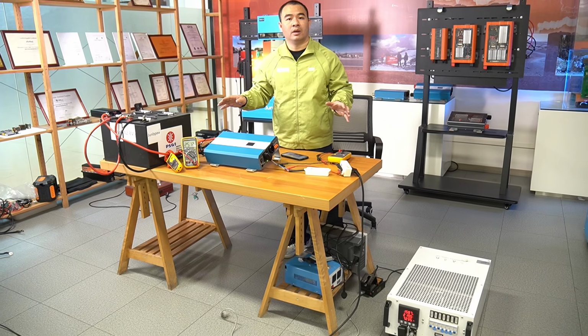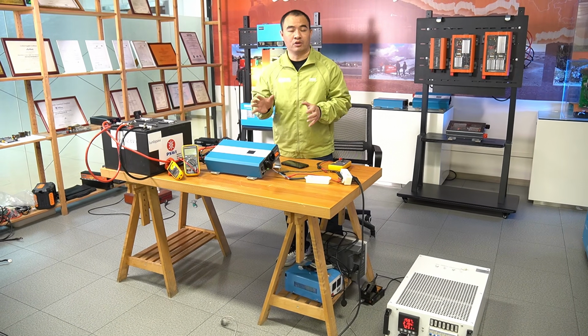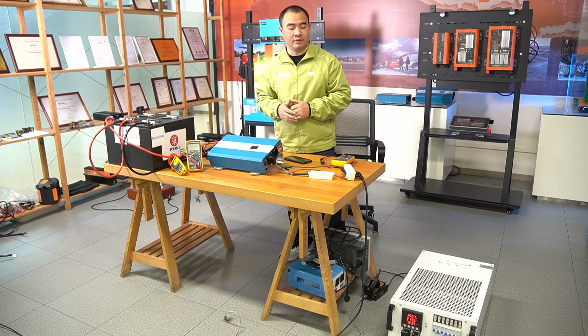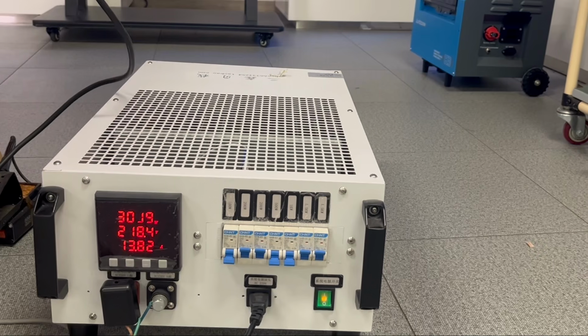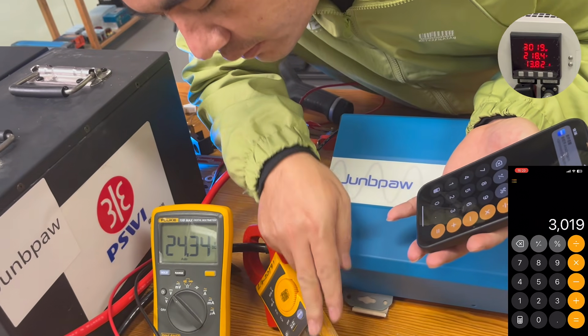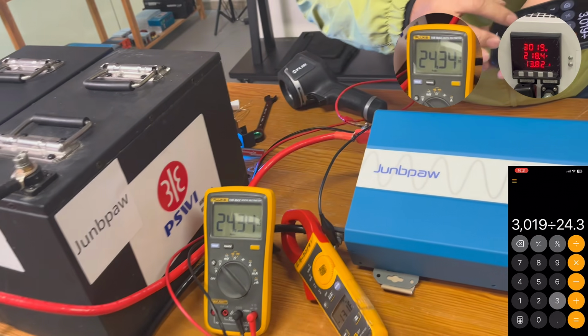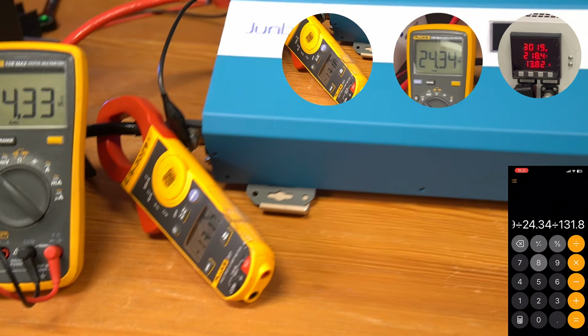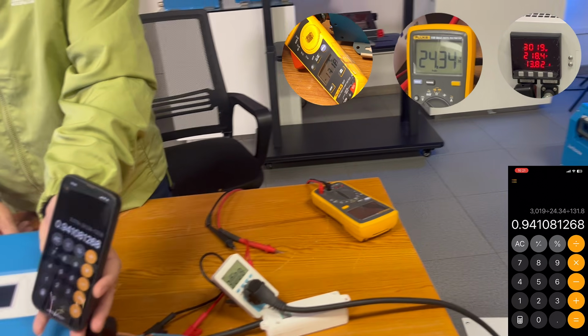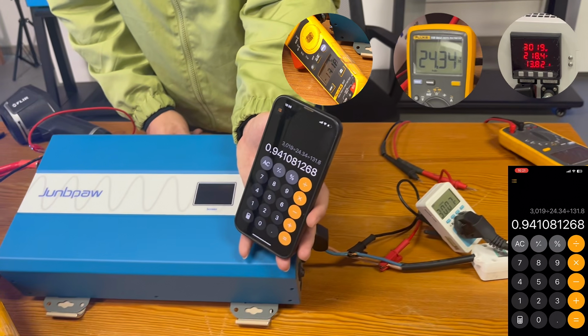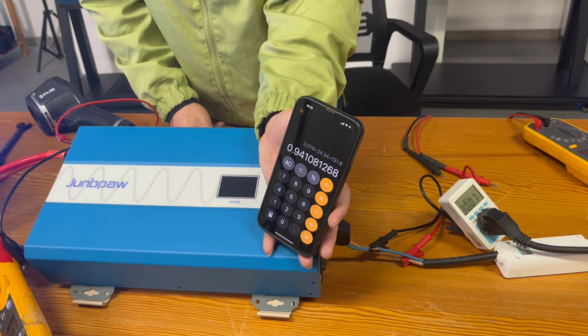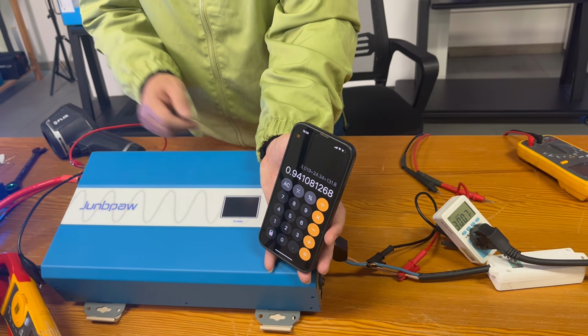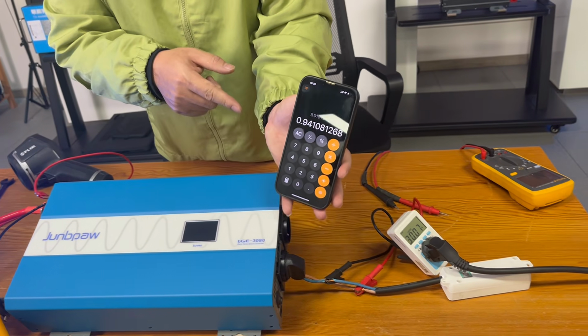Let's calculate it. Efficiency equals total output power divided by input voltage divided by input current. Let's plug the numbers into the formula. 3019, 24.34, 131.8. Okay, the result is 0.941, which is 94.1%. This is the working efficiency of this 3080 watt inverter under full load condition.